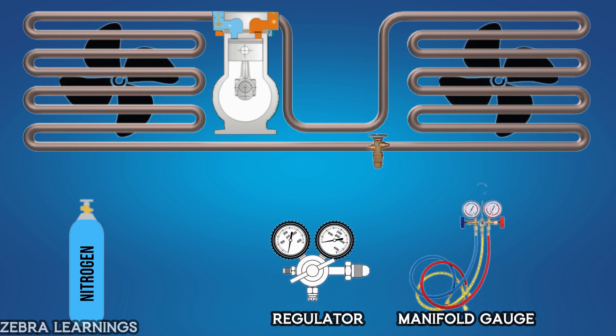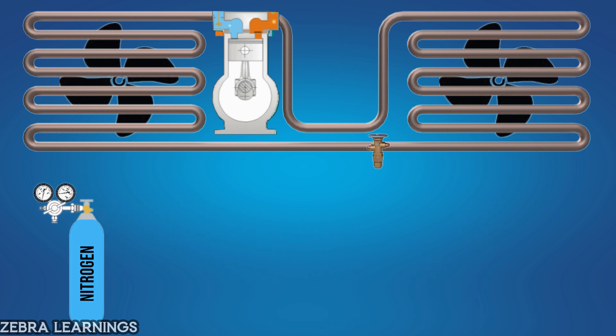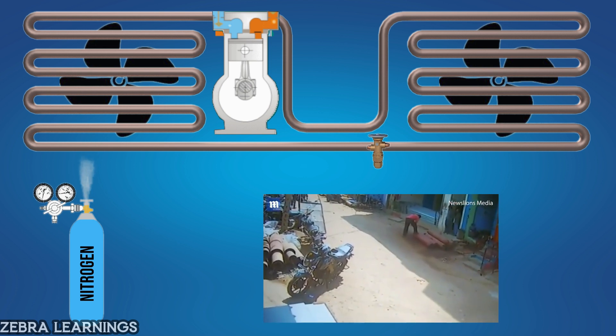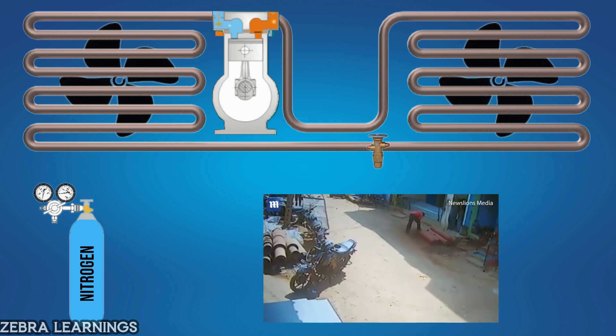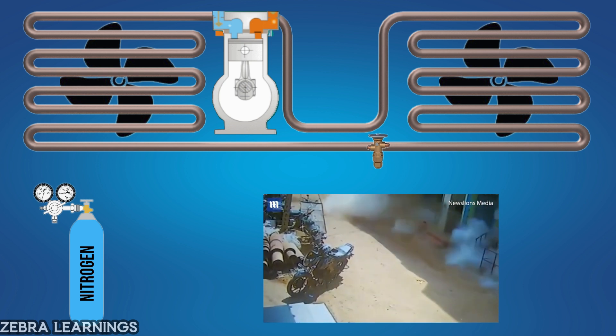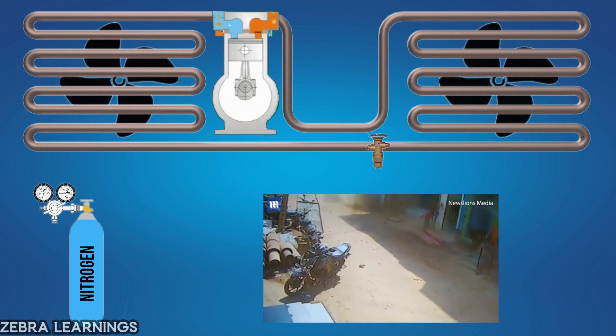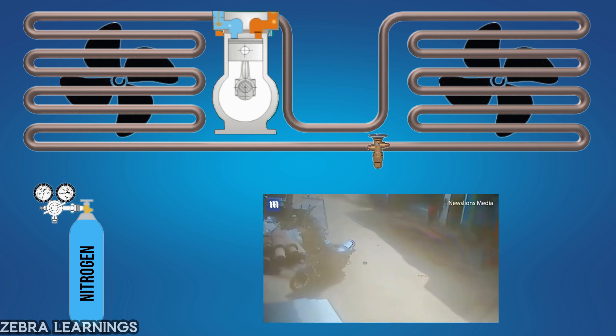First, connect the regulator to the nitrogen cylinder. Always remove the regulator from the cylinder when you are finished using it. Leaving the regulator attached to the cylinder increases the risk of a nitrogen leak, as any accidental impact can damage the regulator, weakening its seals and connections. Nitrogen is stored in cylinders at very high pressure and a leak can be dangerous. Therefore, always remove the regulator when you are finished using it.